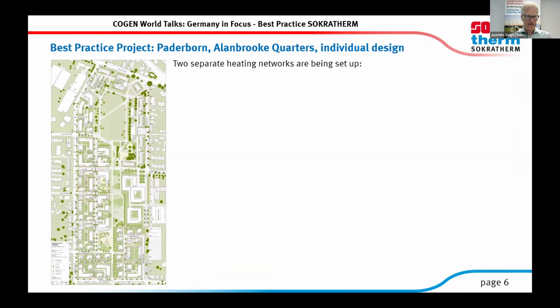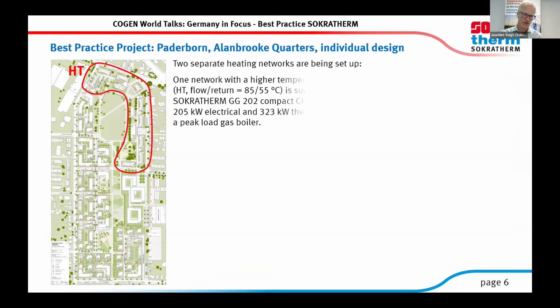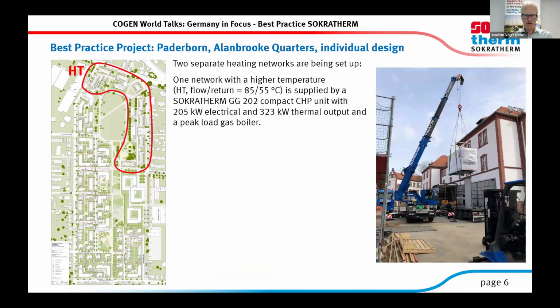To provide the whole area with heat, two separate heating networks are being set up. The first one is a network for higher temperature, so flow temperature is 85 degrees, return 55 degrees Celsius, and this network is supplied by a Sokratherm GG202, a compact CHP unit with 205 kilowatt electric, 323 kilowatt thermal output, together with a peak load gas boiler.